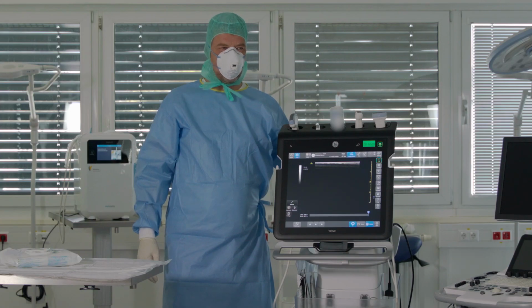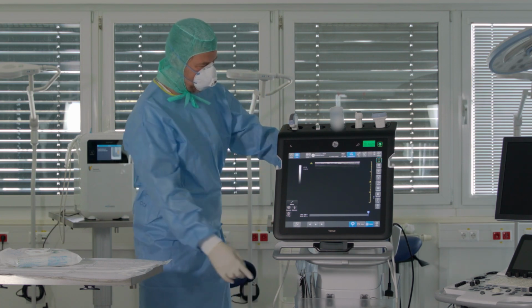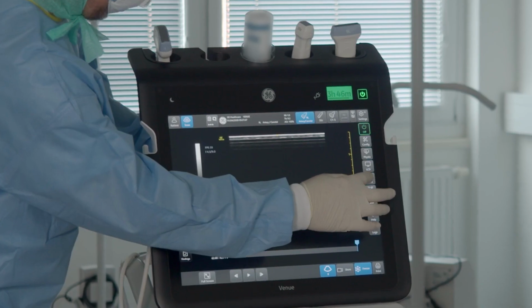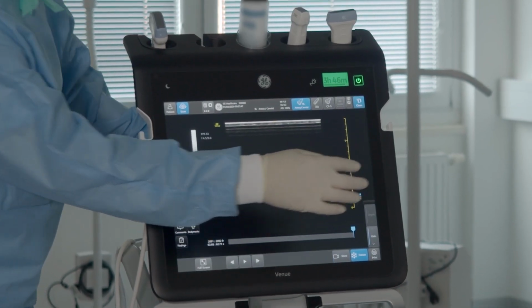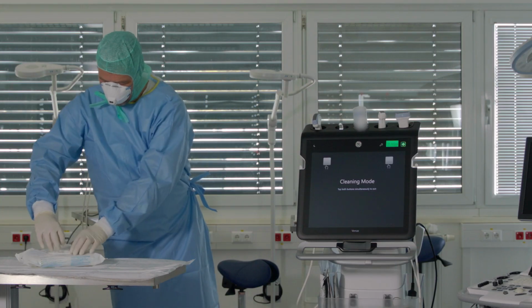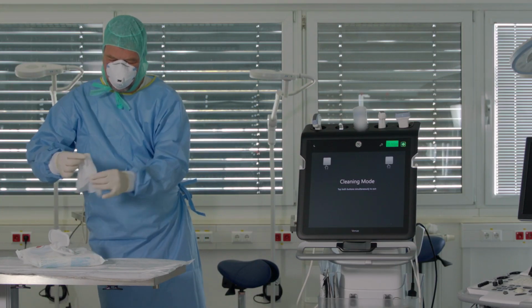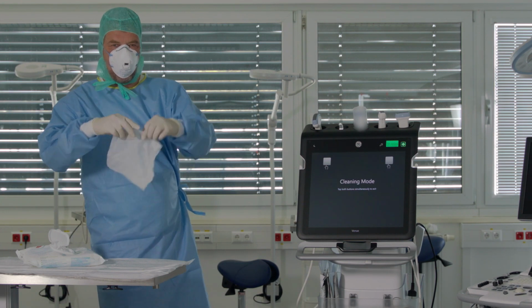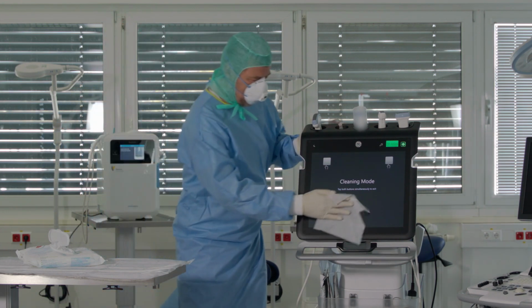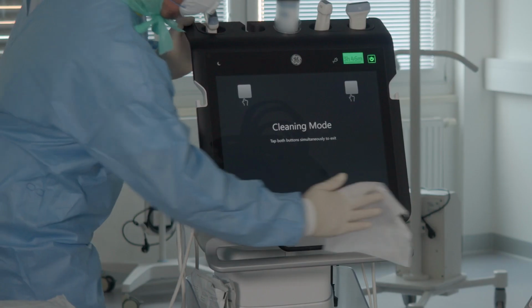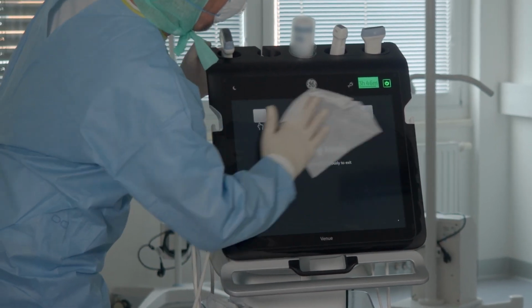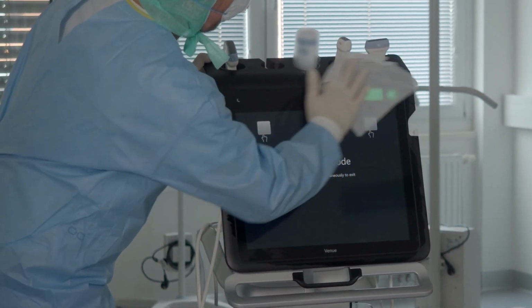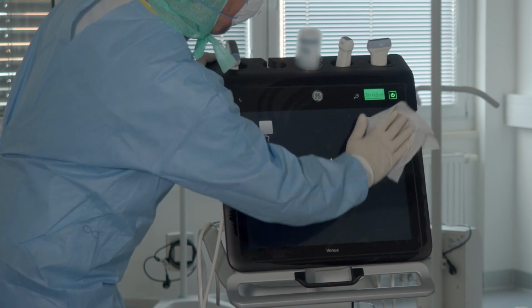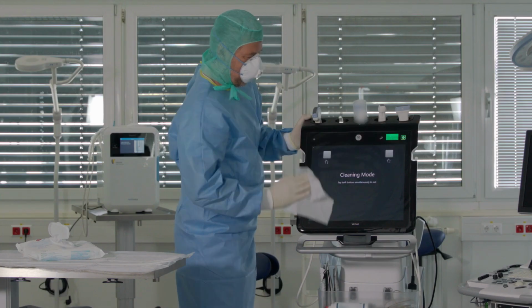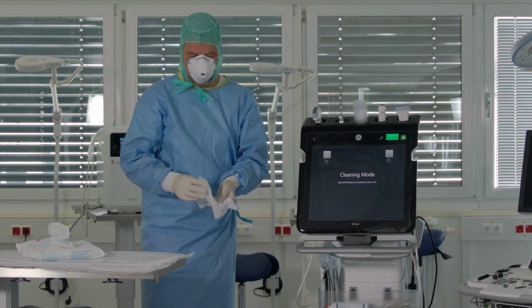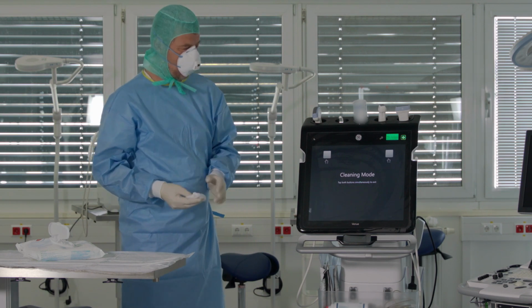Prior to cleaning these touchscreen displays, you may want to put the system in cleaning mode, if available. Then wipe the screen and its surroundings gently. Be sure to use a systematic approach and wipe the entire system. Leave the display to dry, and only then turn the screen back on.